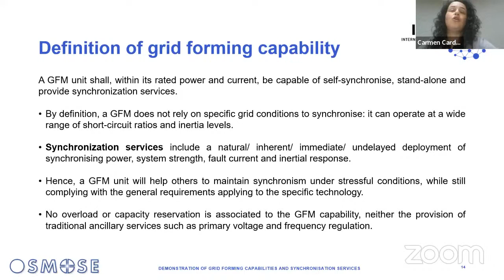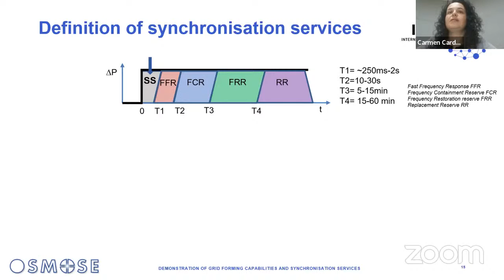So the idea is to fill this gap that we have today in the definition of services, in what happens when you have a disturbance, between time zero and the time that some units start providing services that exist today or will soon exist, like frequency response, frequency containment reserve, frequency restoration reserve, or replacement reserve. So these are the three layers of ancillary services that are well defined today. Fast frequency response is an ancillary service deployed in some countries and still to come, but what we propose is to have the synchronization services, which are the ones missing to cope with the first instance of a transient response. And today, where we can fit these synchronization services in our industrial framework is in what we call non-frequency ancillary services, which have included until today steady-state voltage control, for instance, and some other capabilities that are requested to operate a resilient system, like black start or island operation.